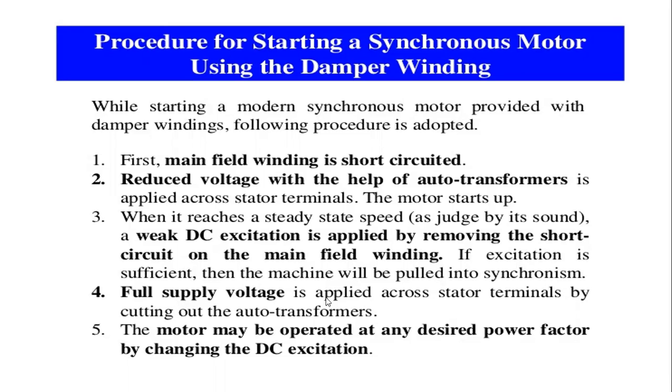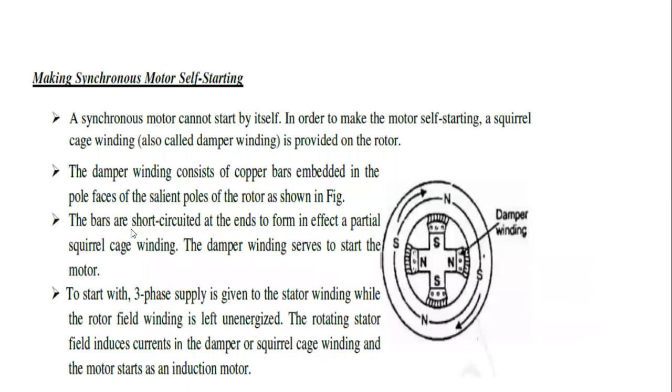Then the full supply voltage is applied across the stator terminals by cutting out the auto transformers. Therefore, the motor may be operated at any desired power factor by changing the excitation, that means at lagging or leading power factors.